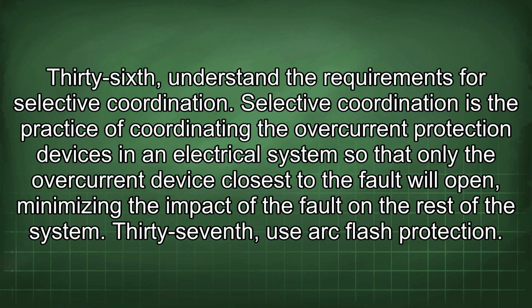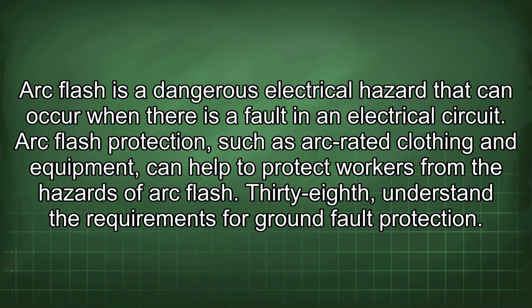36. Understand the requirements for selective coordination. Selective coordination is the practice of coordinating the overcurrent protection devices in an electrical system so that only the overcurrent device closest to the fault will open, minimizing the impact of the fault on the rest of the system. 37th, use arc flash protection. Arc flash is a dangerous electrical hazard that can occur when there is a fault in an electrical circuit. Arc flash protection, such as arc-rated clothing and equipment, can help to protect workers from the hazards of arc flash.